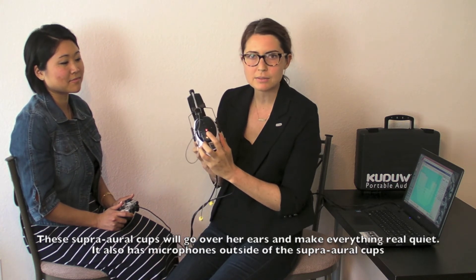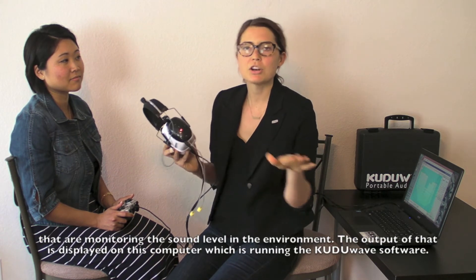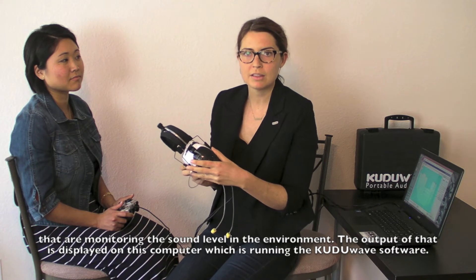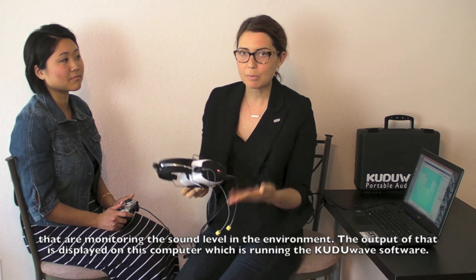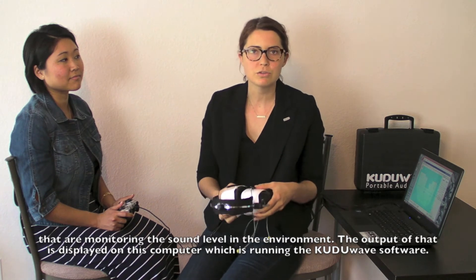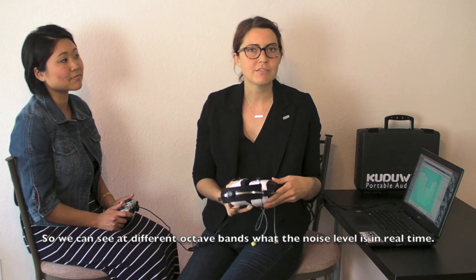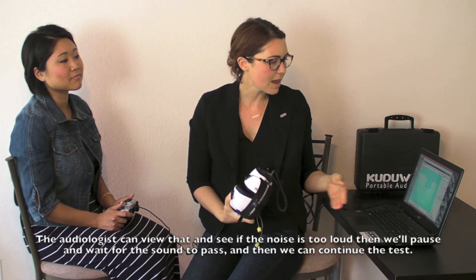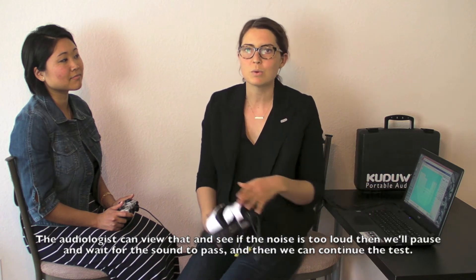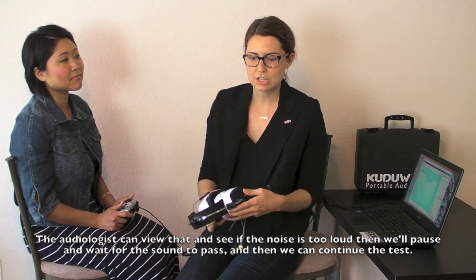It also has microphones outside of the supra-aural cups that are monitoring the sound level in the environment, and the output of that is displayed on this computer, which is running the Kudu Wave software. We can see at different octave bands what the noise level is in real time, so the audiologist can view that and see if the noise is too loud, then we'll pause and wait for the sound to pass, and then we can continue the test.